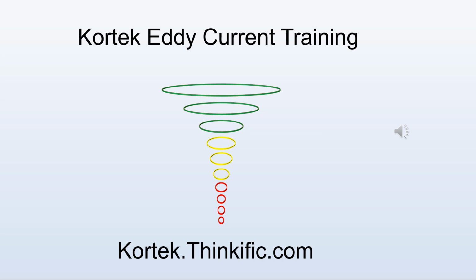That being said, eddy current is a versatile technique that can be used not only for flaw detection, but can also be used to perform various material assessments related to conductivity, permeability, or dimensional characteristics. Eddy current is very sensitive to small discontinuities at or near the test part surface. Eddy current also provides immediate results that are ready to evaluate. Eddy current instruments are very portable, and minimal test object surface preparation, if any, is required.